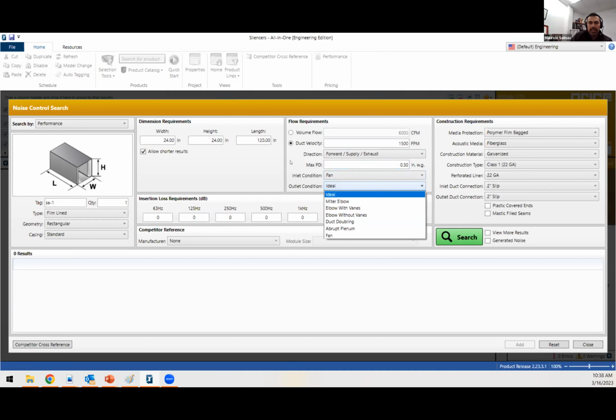The outlet one, if you want to keep a straight silencer, then you probably have an elbow, right? Either with or without vanes. Now, if it's coming from the vertical, most likely you don't have a lot of room, right? So then you can play with that. Now, what the elbow is good for instead of a straight silencer, and I'm going to show you what that is if you were to select this, and let's say you have that performance required from an acoustician already, and this is the first type of selection that you could do. You already know the performance that you need, so that's kind of what we're doing here. Assuming that that's the case, a polymer film bag, because this is going to go into, let's say, a pre-operating room, so it's not as critical. You can have fiberglass. It is on the vertical.